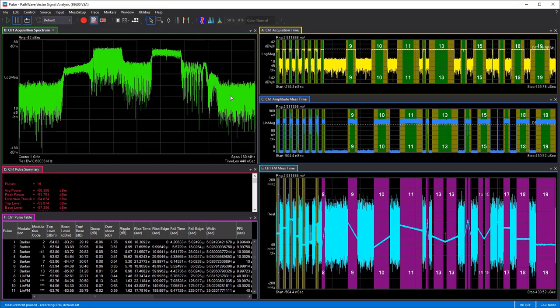On the right-hand side we can see our acquisition time, which shows amplitude versus time of the pulses we're acquiring. Beneath that we have amplitude measure time, and we'll distinguish the differences between these, as well as FM measure time — showing what frequency modulation characteristics are happening over time. All of these are correlated with the number of pulses captured; you can see pulse nine highlighted across all traces, so you get a lot of correlation between them.